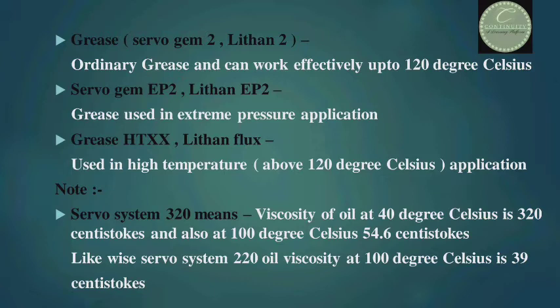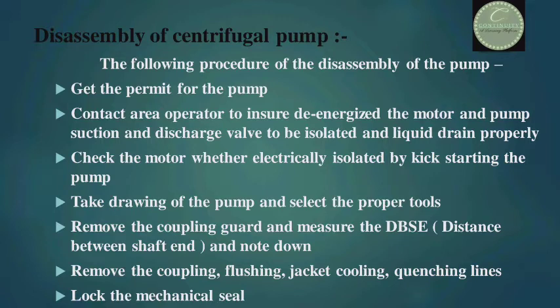Grease types include: Servo Gem 2 (Lithon 2), which is ordinary grease and can work effectively up to 120°C; Servo Gem EP2 (Lithan EP2), used in extreme pressure applications; and Grease HTXX (Lithon Flux), used in high temperature applications above 120°C. Note: Servo System 320 means viscosity of oil at 40°C is 320 centistokes and at 100°C is 54.6 centistokes. Servo System 220 oil viscosity at 100°C is 39 centistokes.